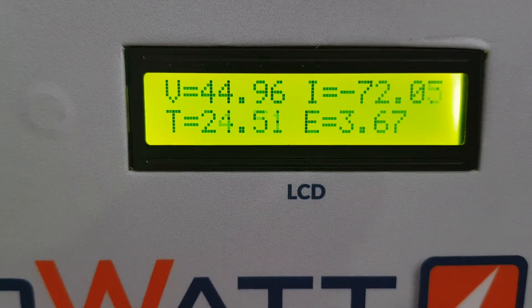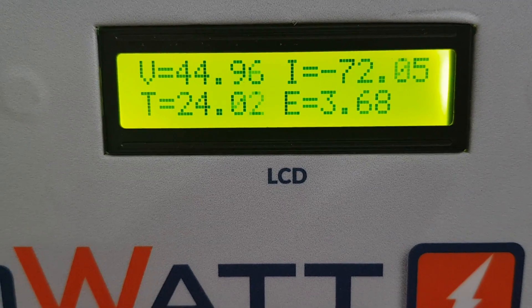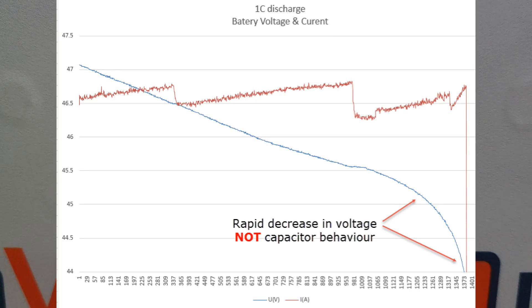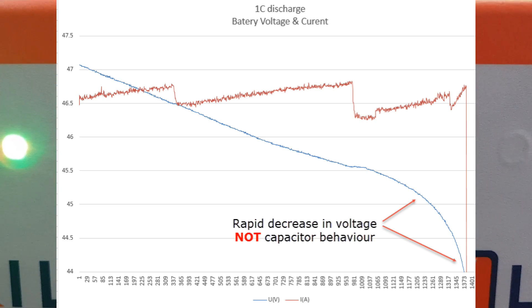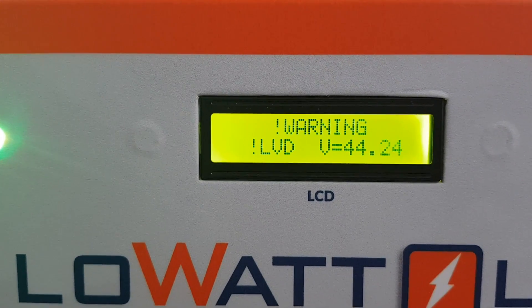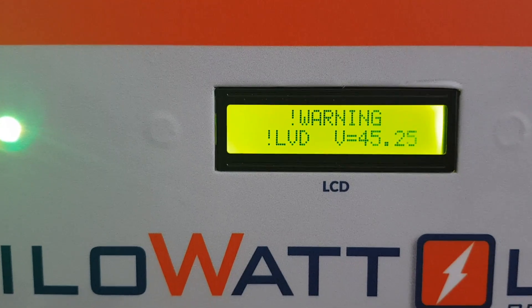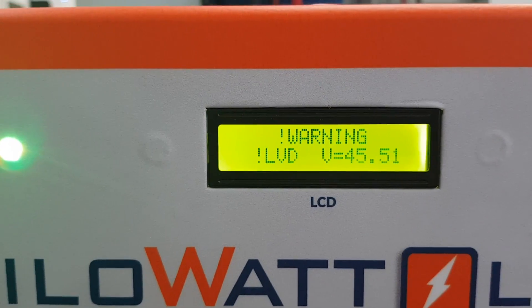We observed a significant stay at about 45 volts for a long time — maybe five minutes — and now we see a sudden decrease in the voltage coming down. The trip level has been set at 44V, so it's coming down very fast now. Now we see a radical acceleration of the voltage at the same current, and it's tripping at 44.1V. We see a bounce-back — it's bouncing back significantly to 45.2V. Exhibiting a big bounce-back characteristic.